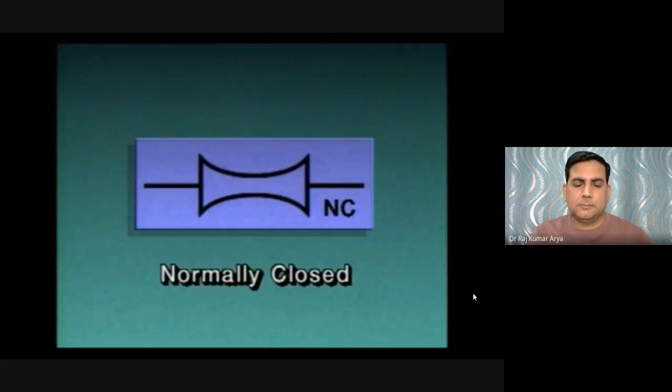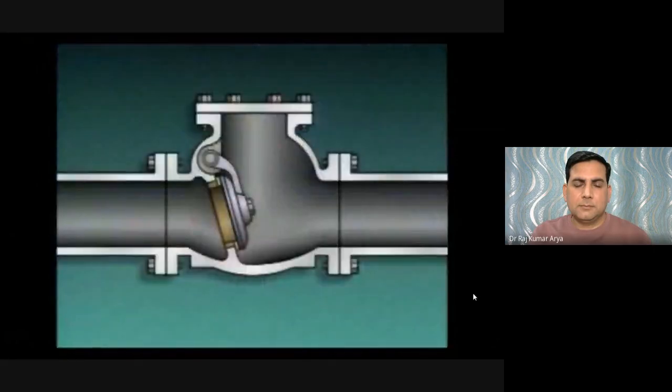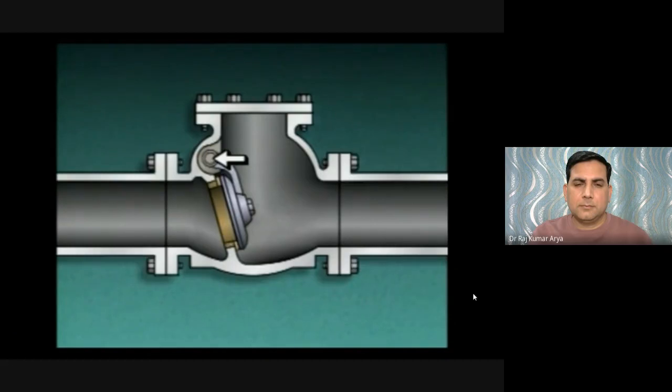Check valves are usually used in piping systems where the reversal or backflow of fluid could upset a process or damage equipment such as a pump. Most check valves operate the same way: fluid flow keeps the valve open, but when flow stops or reverses, the valve closes. A swing check valve consists of a valve body, a seat, a disc, an arm, and a pivot pin.